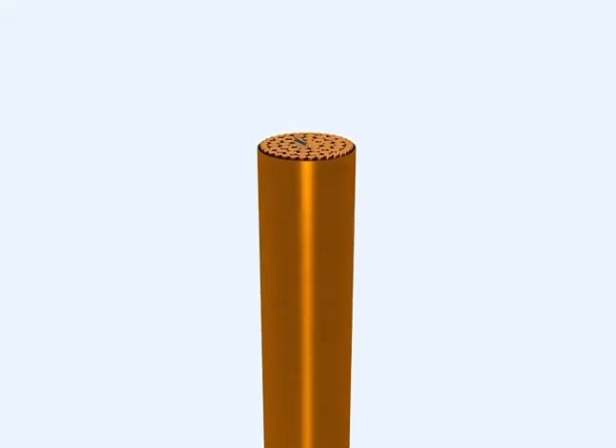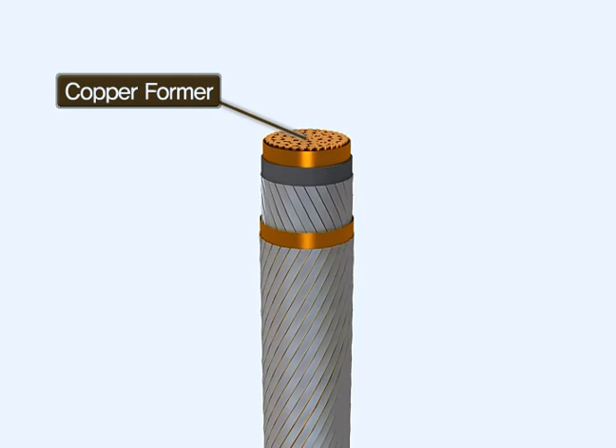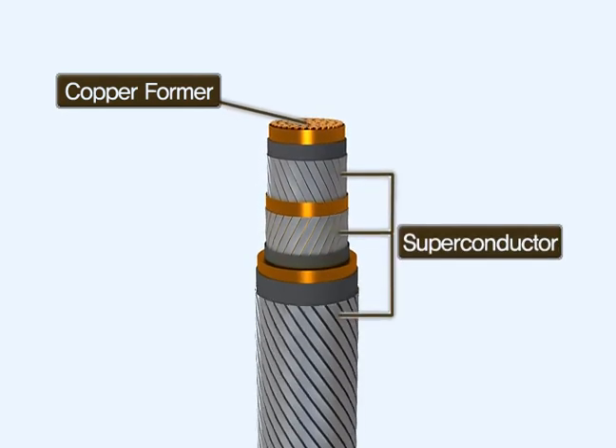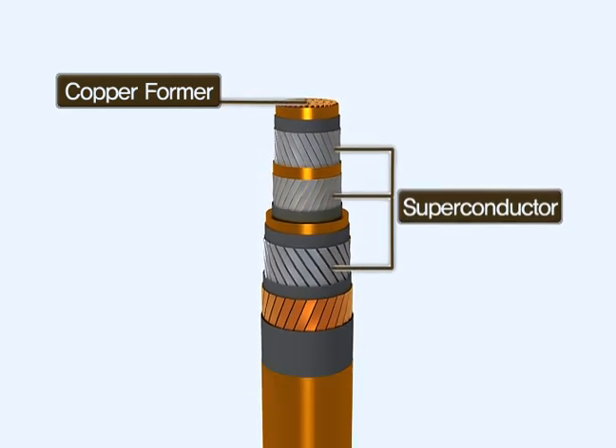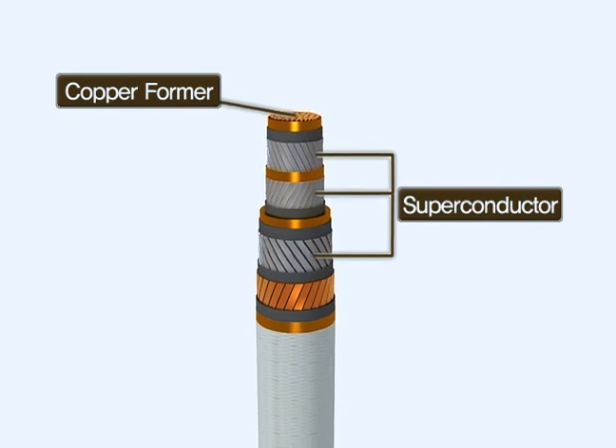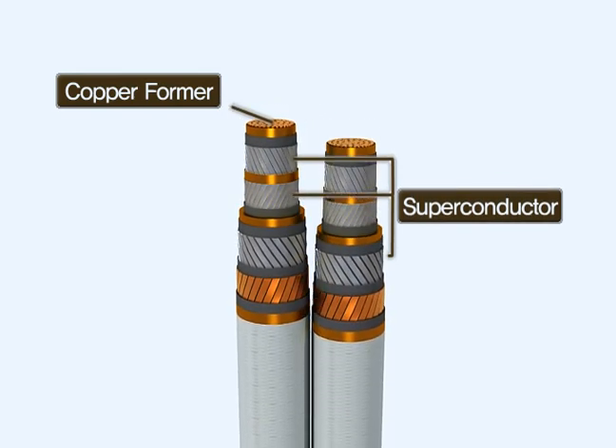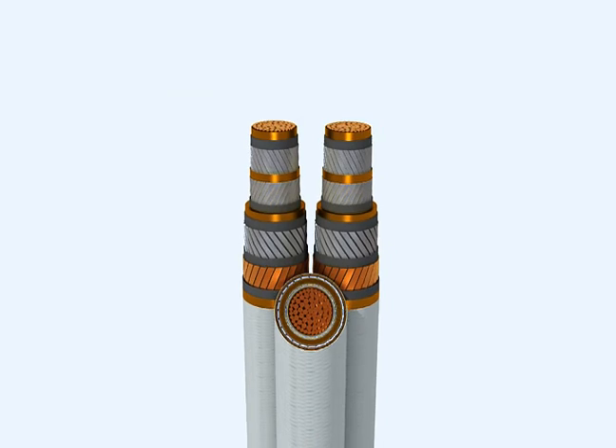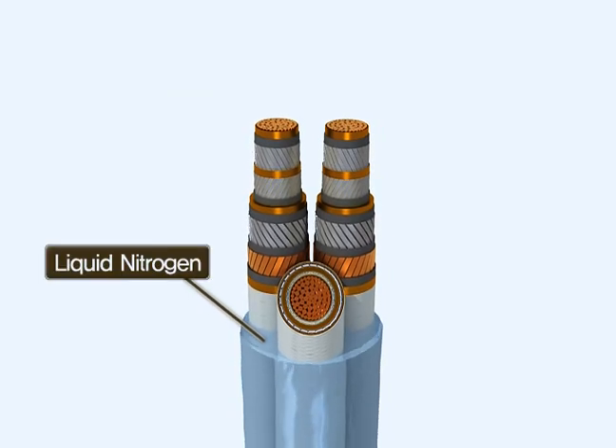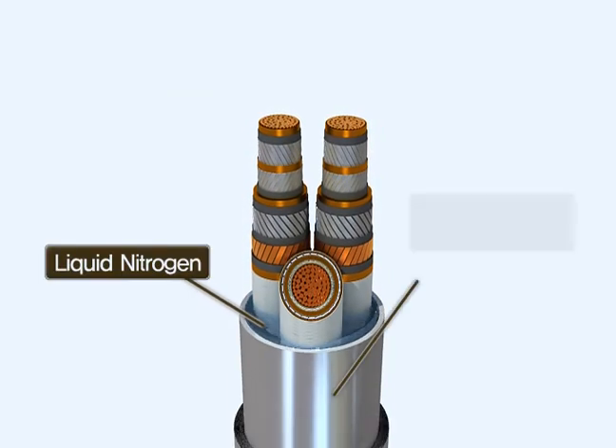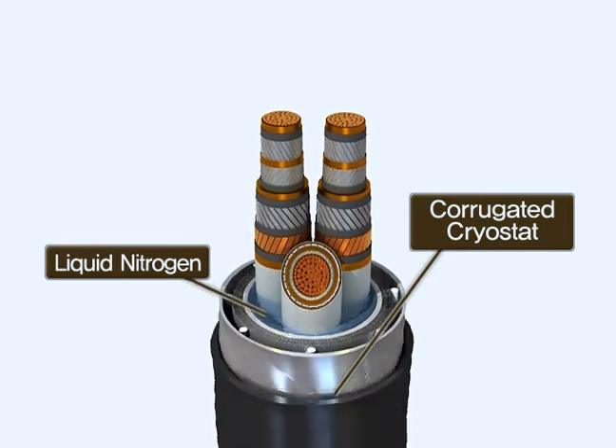A superconducting cable consists of mainly 5 parts. A copper former in the center is for short-circuit currents. Layers of superconducting tape are wound around the strands on the former, which forms an insulation core. Around the 3 cable cores flow liquid nitrogen for system cooling. The corrugated pipes and jacket finally surround it all.